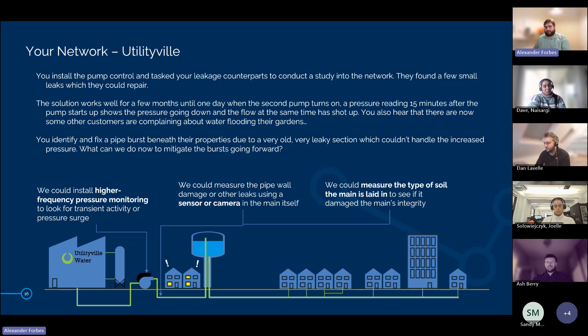The high frequency pressure monitors show you that when the pumps turn on and off, there's a significant slam from the non-return valve closing, as well as a large pressure surge as the flow gets up to its steady state. We choose to repair the sections of main which were leaking, but we need to maximize the lifespan of the main because this was an expensive problem to have. How can we extend the longevity of the main through control alone? And again, if you've got any thoughts, pop them in the chat.